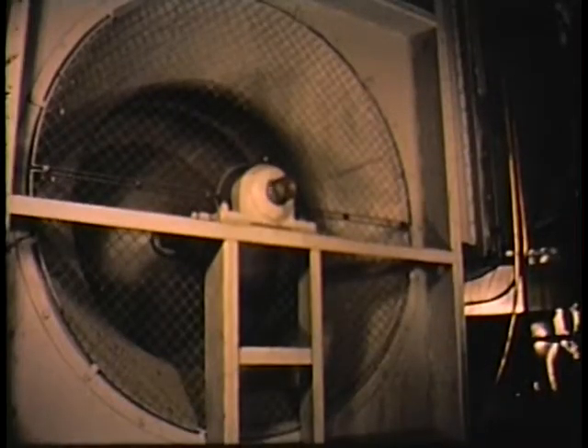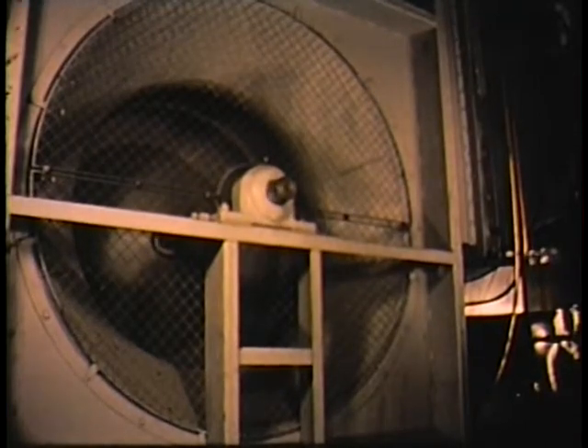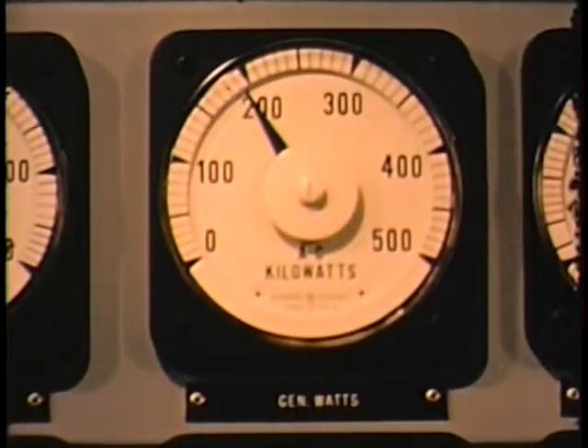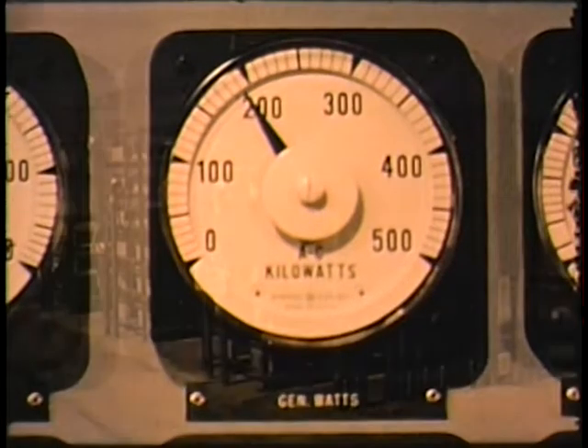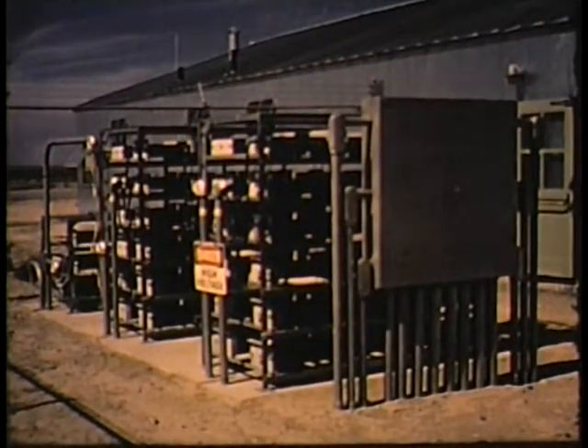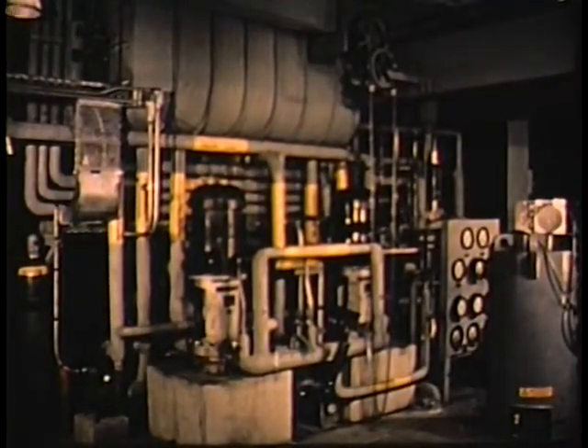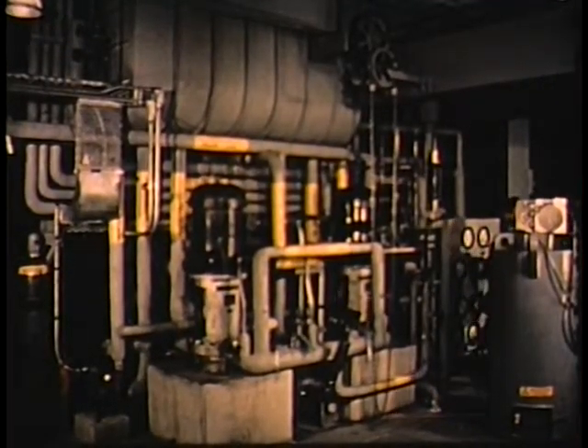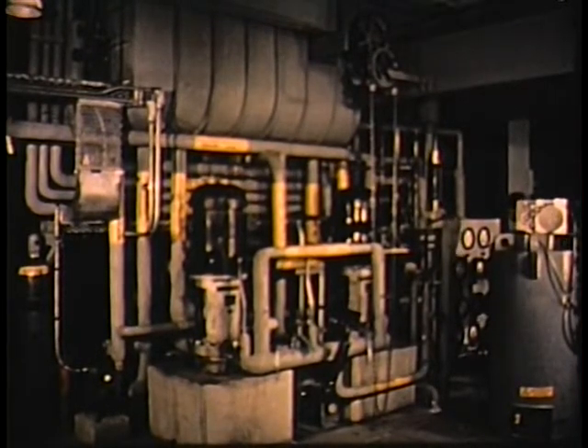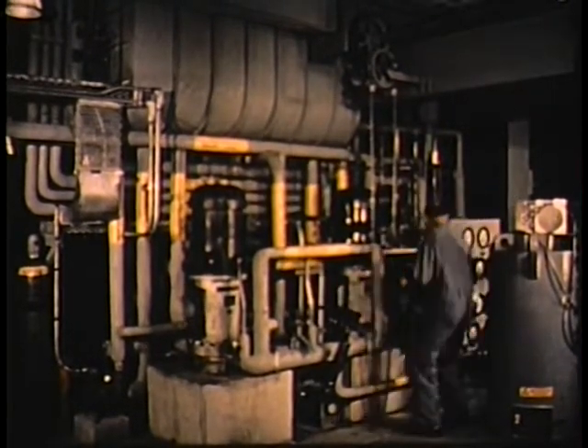Air cooling is used because of the likelihood of a limited water supply in sites where such a nuclear power plant might be used. The condenser and fan are sized to permit a normal full power production of 200 kilowatts of electricity plus auxiliary power and space heat at an outside air temperature as high as 60 degrees Fahrenheit at a sea level site. The condensate from the main steam condenser flows by gravity to the hot well, from which it is returned to the pressure vessel by a feedwater pump.